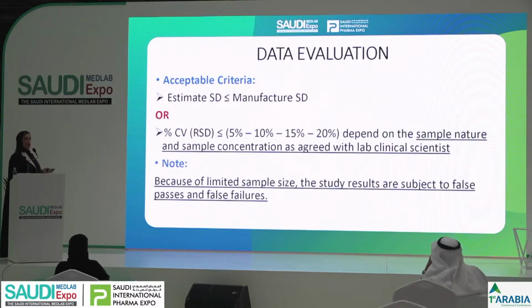My recommendation in my lab is always to go with 10 and 15. This is what the 5, 10, 15 are: the margin of error that I can tolerate in my lab. I don't want to make it very big, and I don't want to challenge myself with a very small margin. I always go with 10 and 15 for all methodology. But if you're running a very small amount or concentration in your lab, go with 20. Give yourself an error margin. Why?